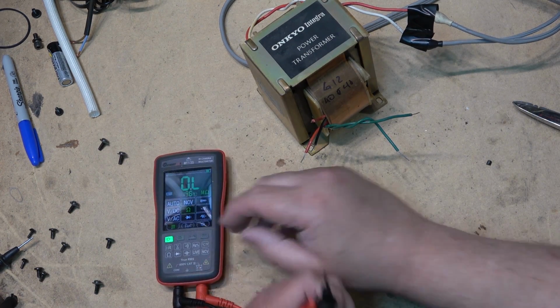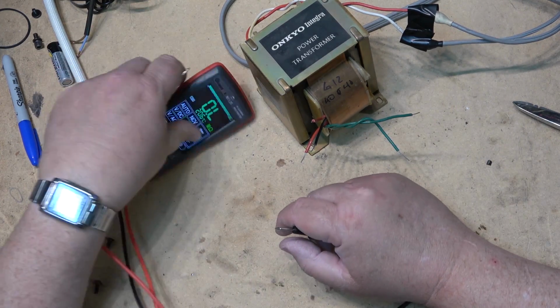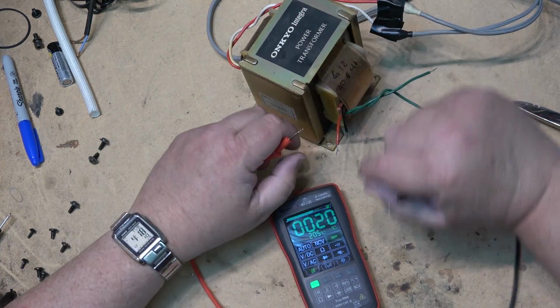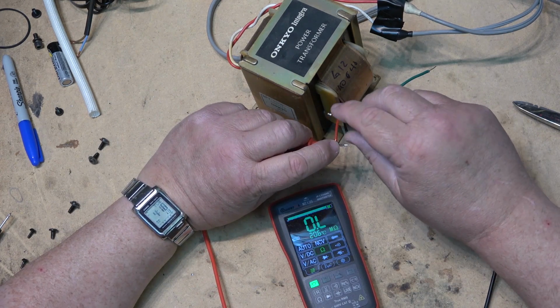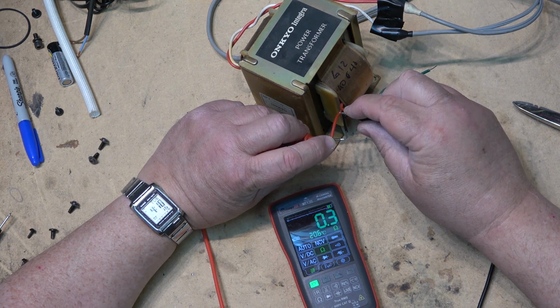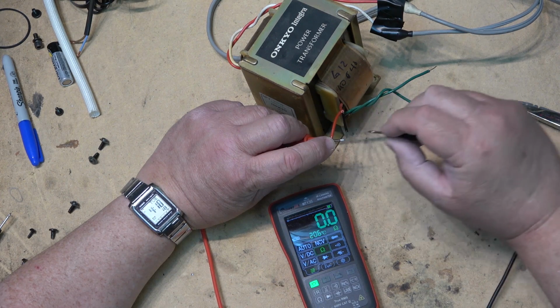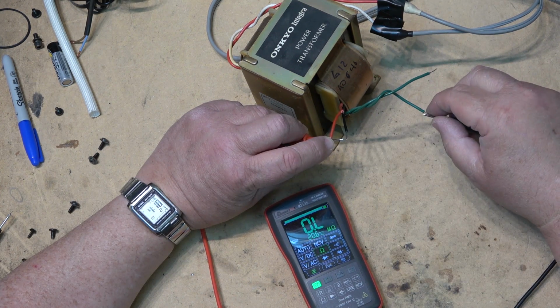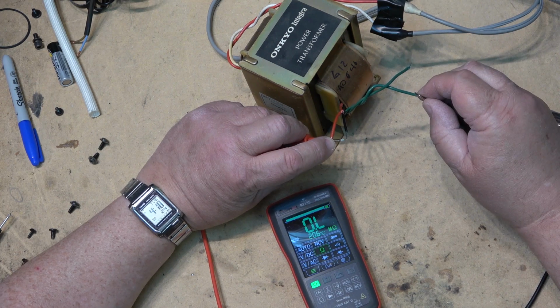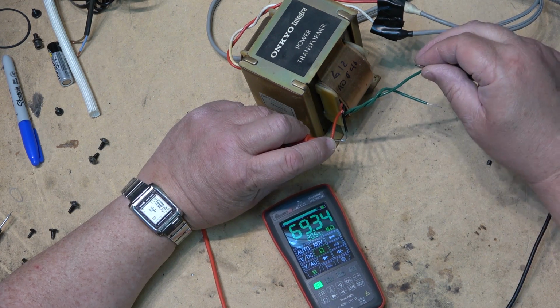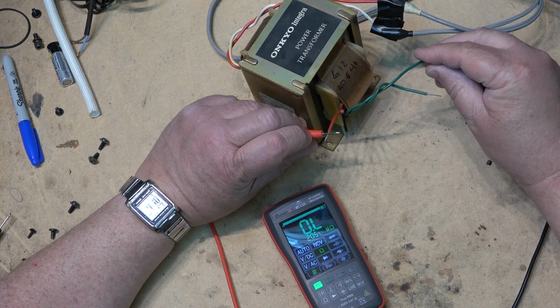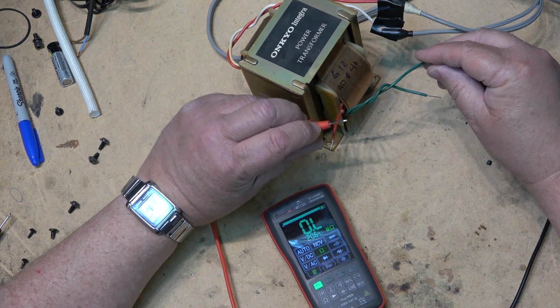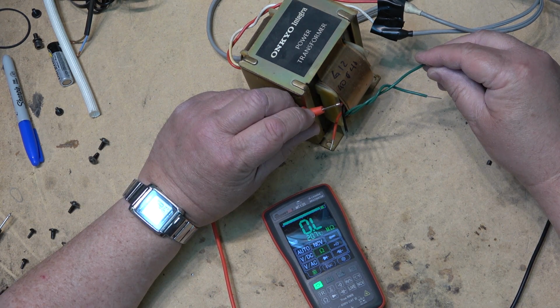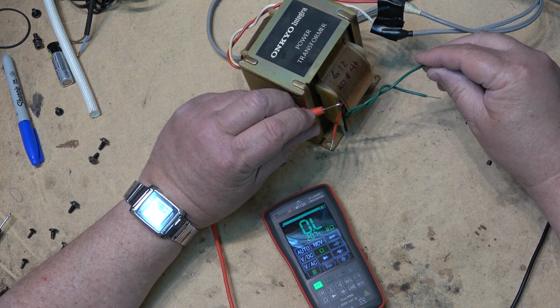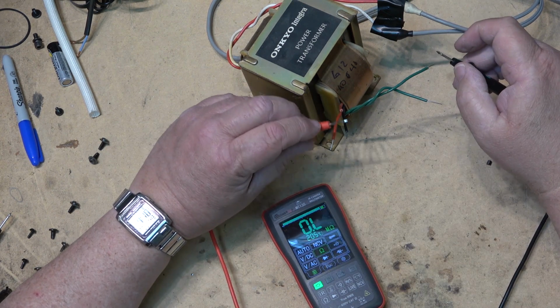We'll unplug that and just check this for ohms. Yeah, they're open, not connected. They're independent windings. I was just getting, this is the mega ohm range, right? So these windings are completely separate. I was just getting induction between the two windings, because it's a high impedance meter, so we're looking at resistance here, and we've got nothing.